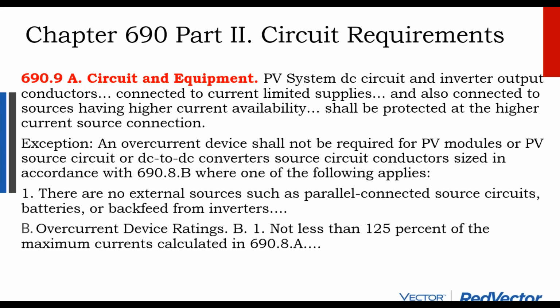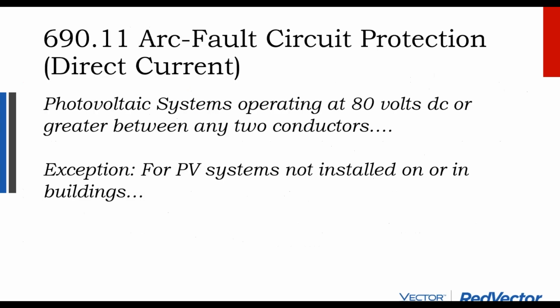Okay, so let's just keep going over this one. Arc fault protection. So systems operating at 80 volts DC or more are now required to have arc fault detection unless it is a ground mount, not attached to a building. So arc fault detection came into being around 2014. Arc faults, we talked about in our introductory to code, they often precede ground faults. So an arc fault is a little gap in the wire, you have arcing across from the wire to the wire, whereas a ground fault is a fault from the wire to a lower voltage reference to ground.